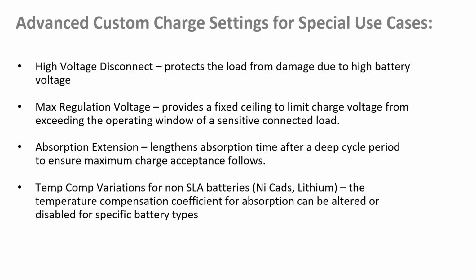Max regulation voltage puts a cap or ceiling on voltage so we never exceed a certain limit. This is helpful for sensitive loads that don't want to see voltage exceeded, such as sensitive telecommunications loads, or in the lower voltage range, something that doesn't want to see anything outside of, say, 10 to 15 volts, a really common window. So we can help assist there.